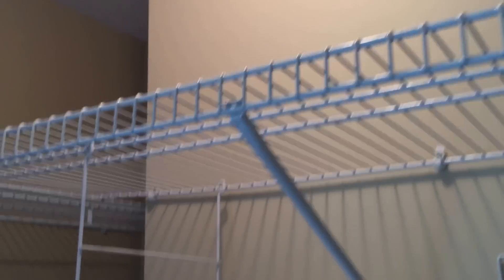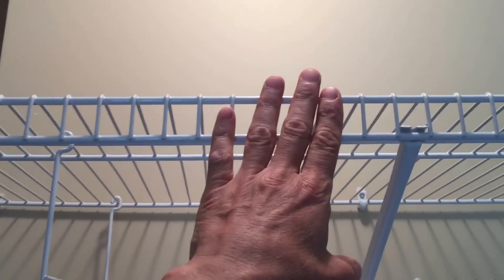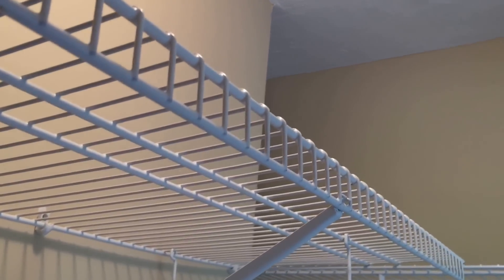This would be a violation of section 410.16(C)(1). Surface-mounted incandescent light fixtures like this have to be at least 12 inches from the storage space. The storage space in this closet extends up from the shelf all the way to the ceiling, so this light fixture has to be moved over this way so that it clears this shelf by at least a foot.